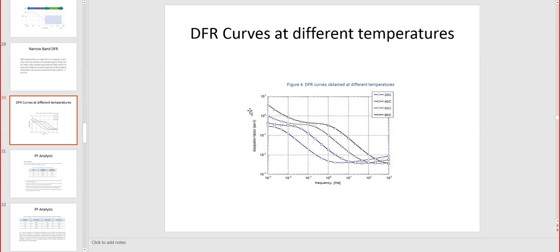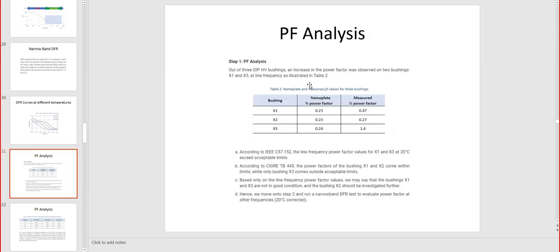That's the graph, so keep in mind, if you do a complete dielectric frequency response, everything at the low frequency will be highly influenced by the temperature, and it will have some influence on the 60 hertz as well. As you can see, 10 to the power of 2 here is 100, so even at that frequency you can have some influence. That's why we need to scale it down to 20.